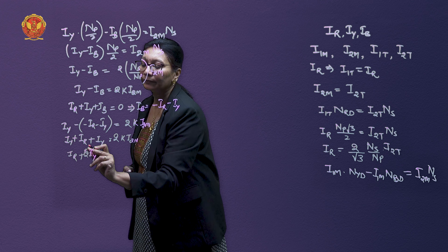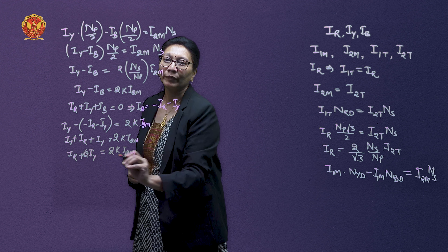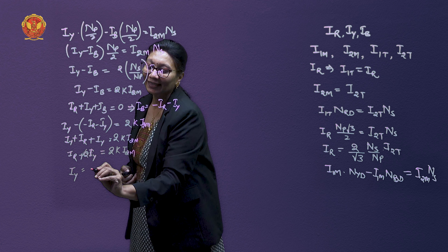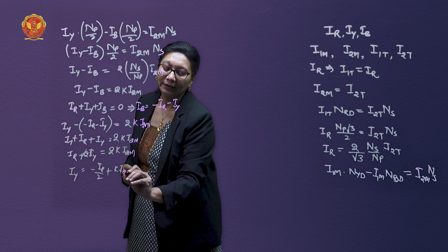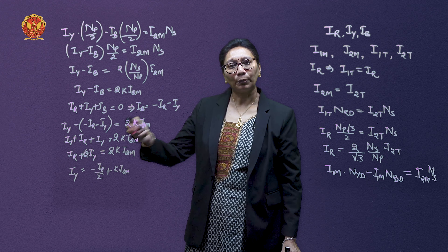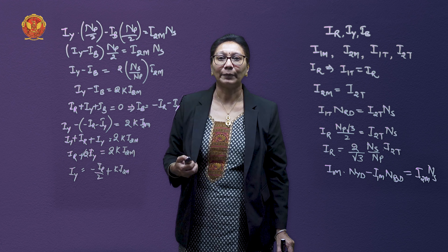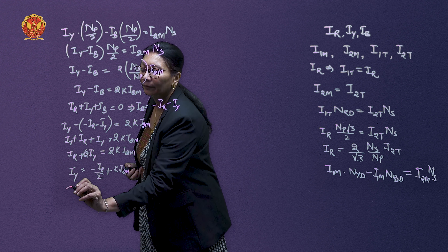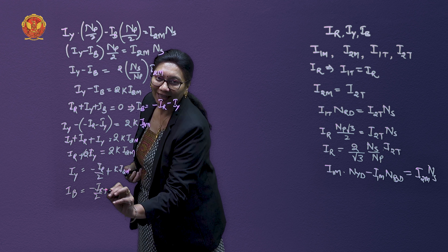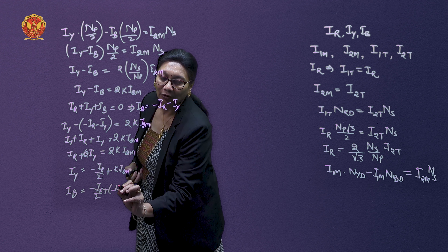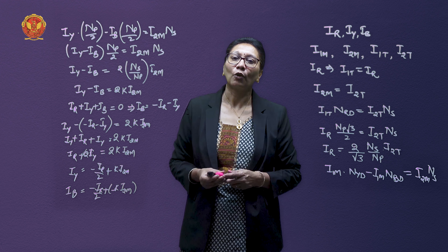From IR + 2IY = 2K × I2M, we get IY = −IR/2 + K × I2M. Substituting this value of IY back into the expression for IB, we also obtain IB = −IR/2 − K × I2M. This way, we can determine the currents for all three phases of the main transformer, and these current equations are valid for both balanced and unbalanced loads.